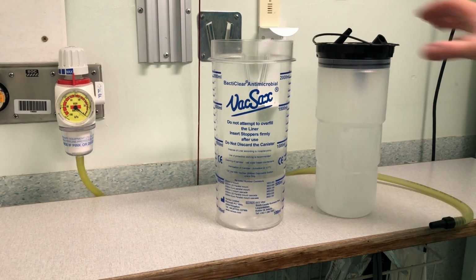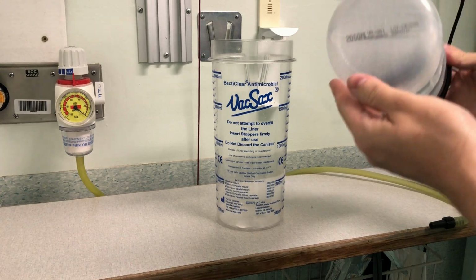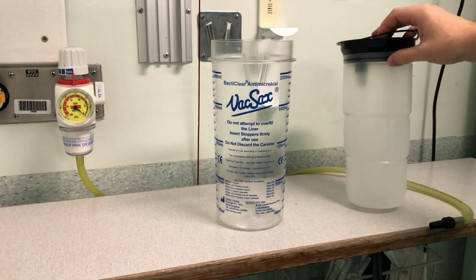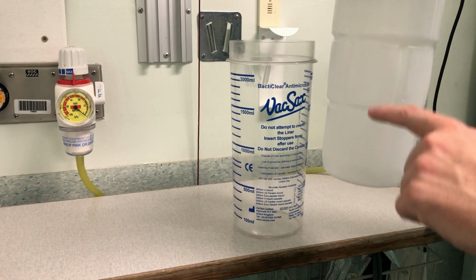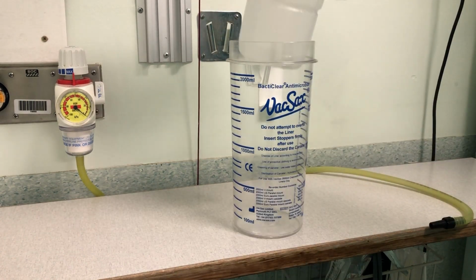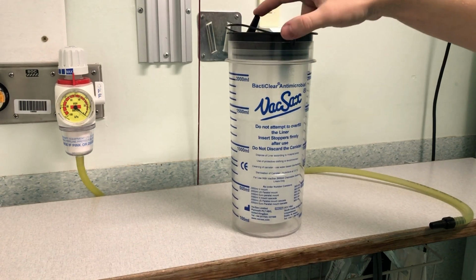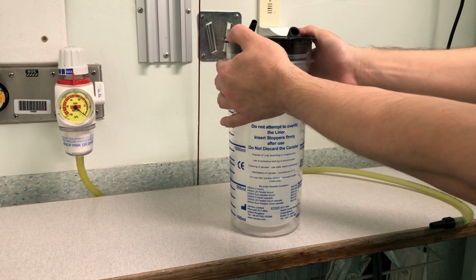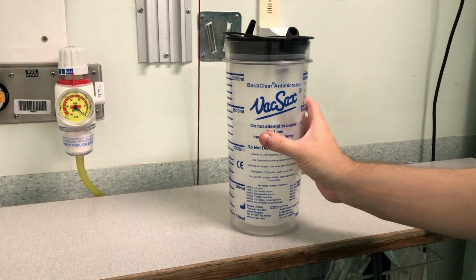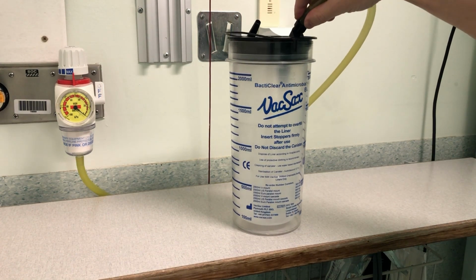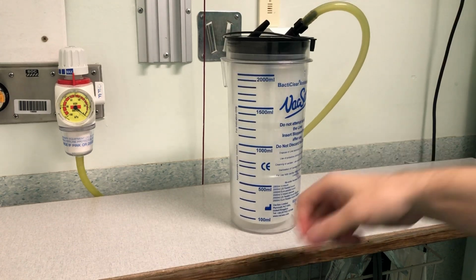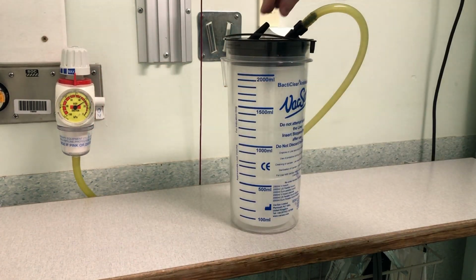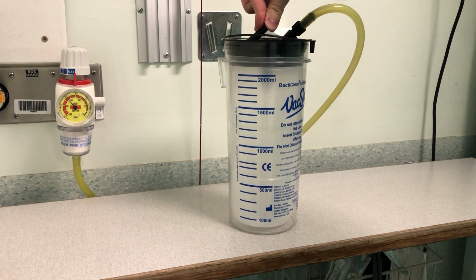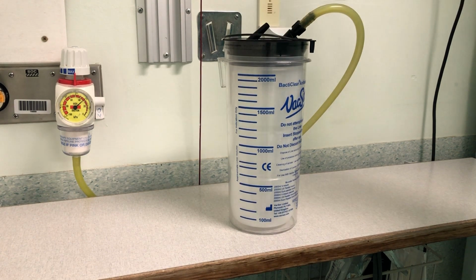So, how to set up the Vacsax liner. Check the liner is within its use date. This can be found printed on the liner and on the packaging label. Ensure that the rigid canister is clean and damage free. Remove the liner from the packaging. The liner is folded for storage. Do not leave the liner folded in the canister. Place the liner into the rigid canister and push firmly, with the patient port facing forward for ease of connection. Push the tapered connector onto the vacuum tubing from the suction controller into the vacuum port with a twisting motion. Turn on the vacuum to maximum and place your finger over the patient port located on the lid of the liner, ensuring a vacuum is present. Vacuum will build up when all parts are assembled correctly. Connect the patient tubing firmly to the patient port to ensure a good fit.